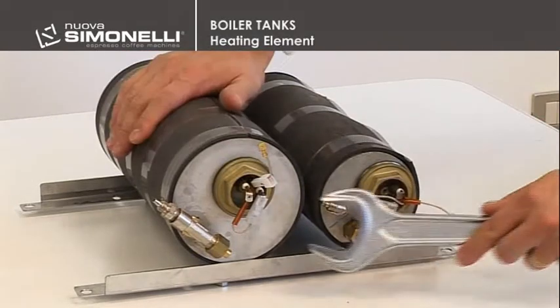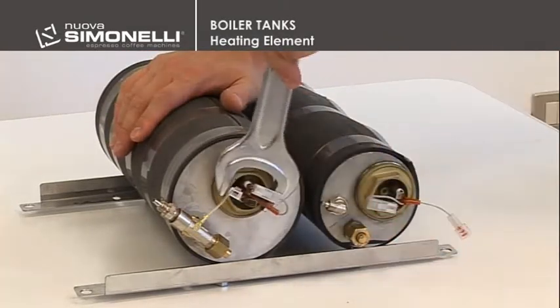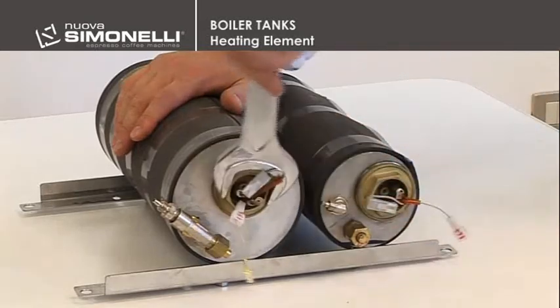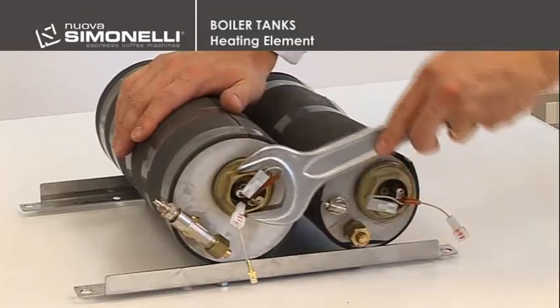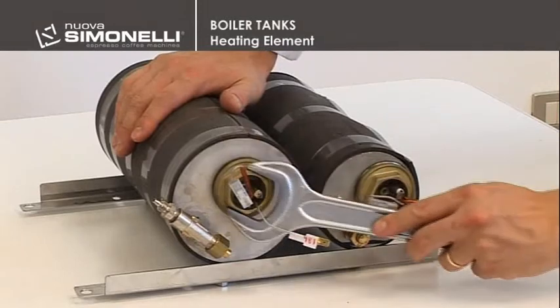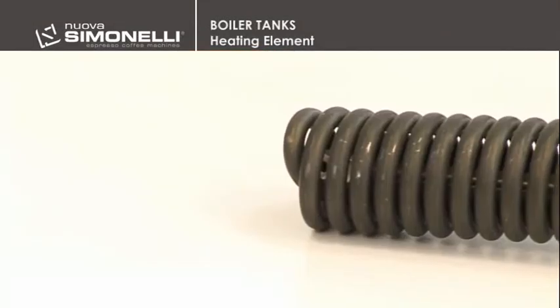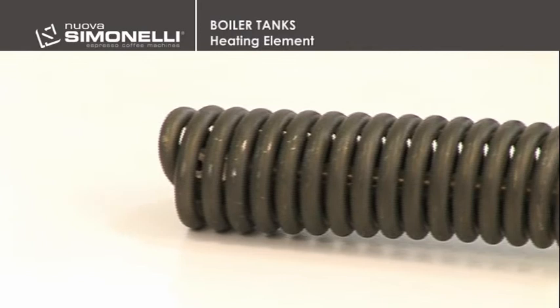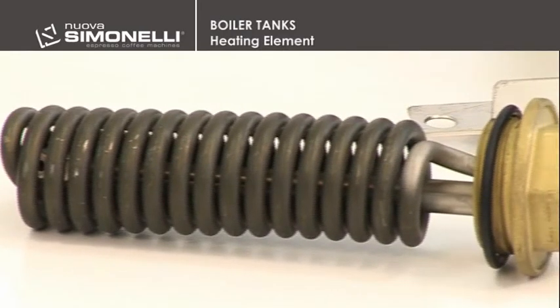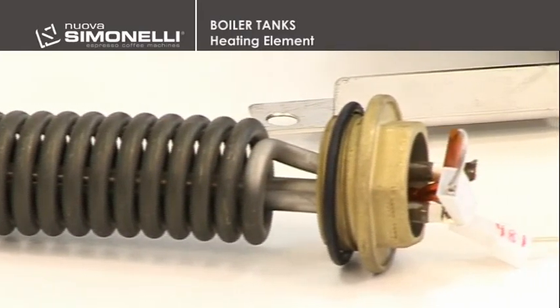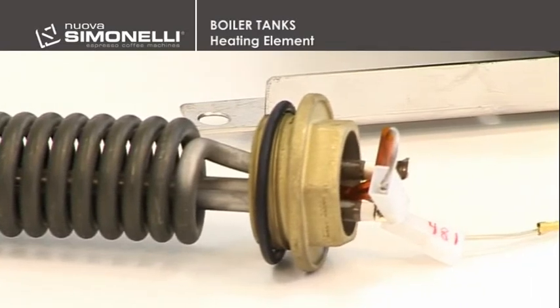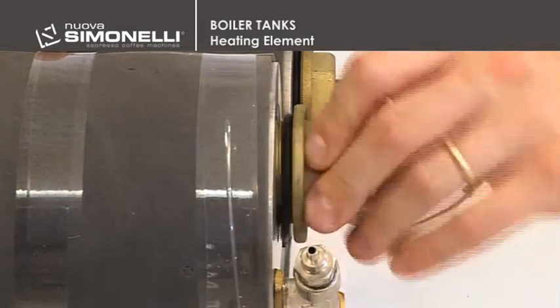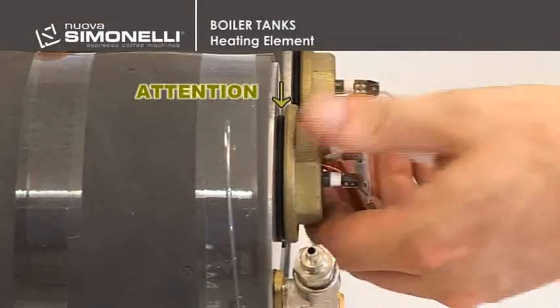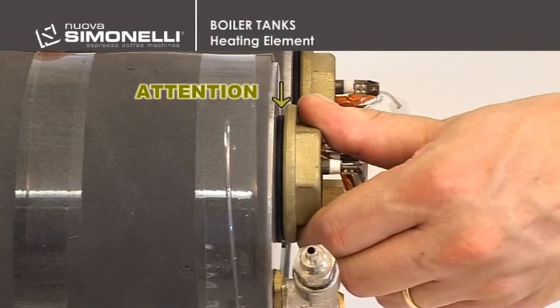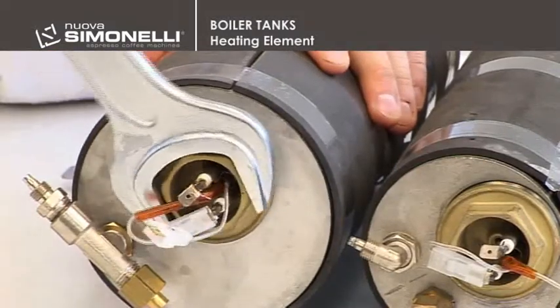Securing the boiler in a vise and using a 37 mm wrench, it's possible to loosen and unscrew the heating element. During the refitting stages, make sure that the seal is completely inside the special seating. Tighten the screw with a 37 mm wrench.